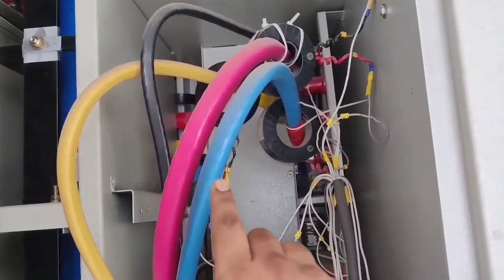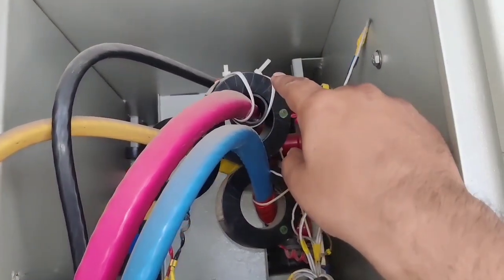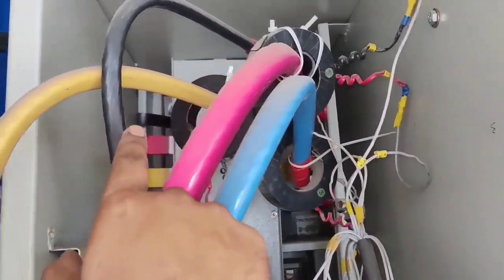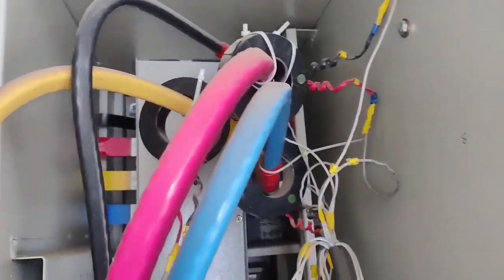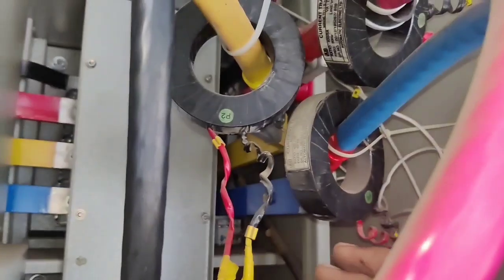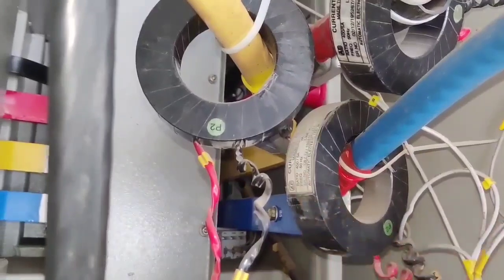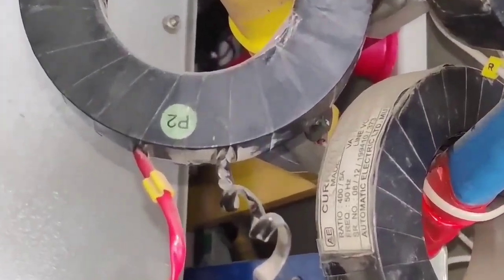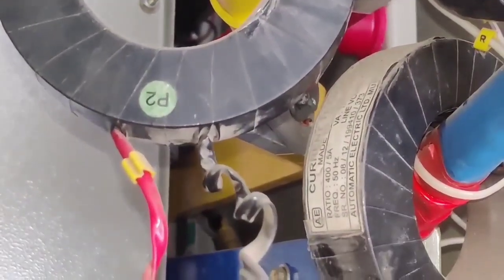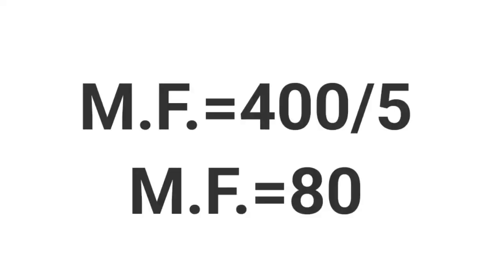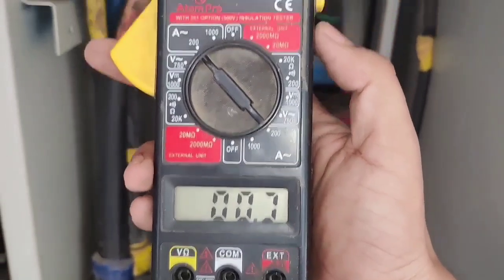You can see we have R, Y, B — 3 phases — and also we have 3 current transformers: one CT for R phase, one for B phase, and one for Y phase. For checking a CT, first you need to identify the ratio of the CT. You can see we are using a 400/5 current transformer. So first, find the multiplying factor: 400 ÷ 5 = 80. The multiplying factor is 80 for this CT.